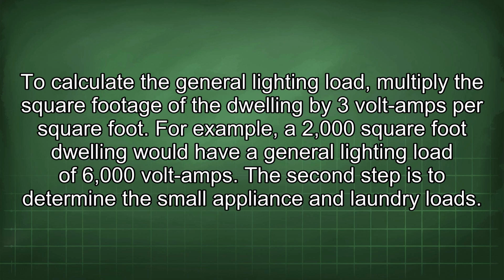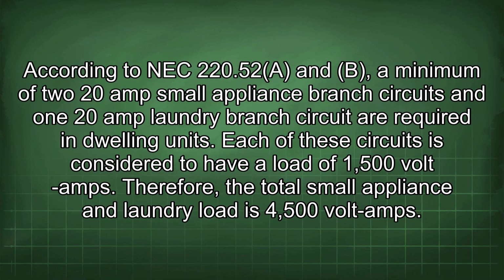The second step is to determine the small appliance and laundry loads. According to NEC 220.52, a minimum of two 20-amp small appliance branch circuits and one 20-amp laundry branch circuit are required in dwelling units. Each of these circuits is considered to have a load of 1500 volt-amps. Therefore, the total small appliance and laundry load is 4500 volt-amps.